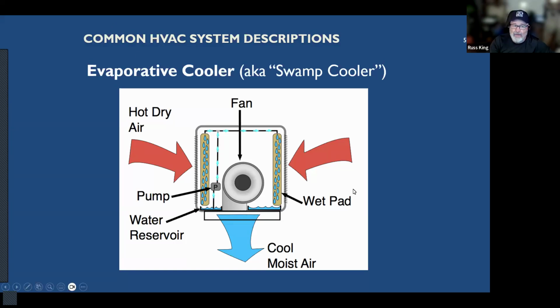It doesn't work on really, really hot days, but it can substantially cool the air coming into the house. So you'll see these used a lot in the desert, not on the hot summer days, but on the milder summer days, when it can actually cool the air. And because the air is so dry in the desert, they work much better. You absolutely do not want an evaporative cooler if you live in Florida or Mississippi, because you're adding moisture to air that's already way, way too humid. And they won't work very well either, because if the air is so humid that the water is not evaporating, the air is not being cooled much. So you're just pushing lukewarm, wet air into your house. But in the desert where it's really dry, these work quite well.